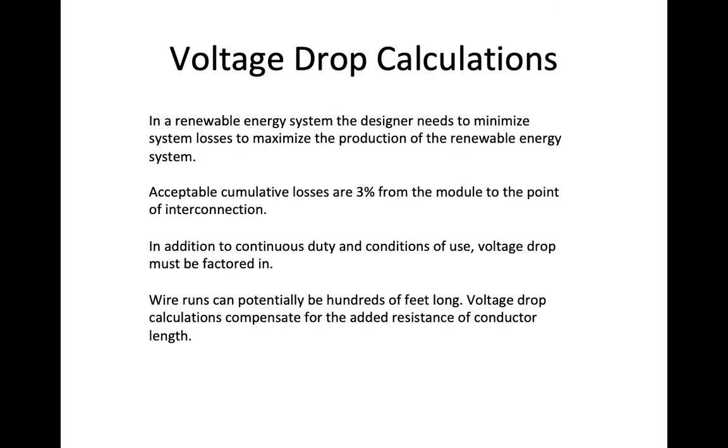Voltage drop calculations: nowhere in the codebook does it say you have to limit voltage drop from point A to point B to a certain percentage. But it is the equipment manufacturers that say you need to supply a certain amount of voltage for their equipment to operate correctly. But it is generally accepted that we will limit voltage drop from 3% to 5%.